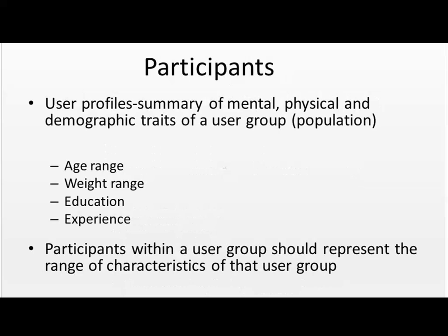The user profiles should have been developed during the human factors program. These are a summary of mental, physical, and demographic traits of a user group. The age range, weight range, the education that is necessary, the experience that's necessary to operate the device.